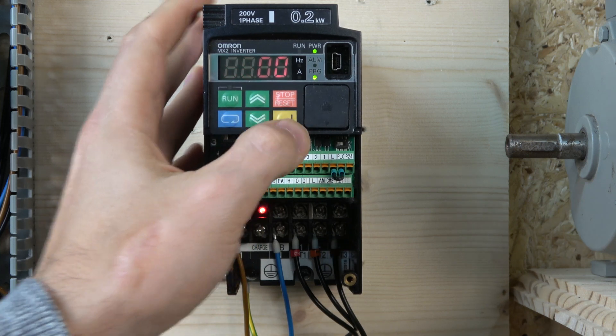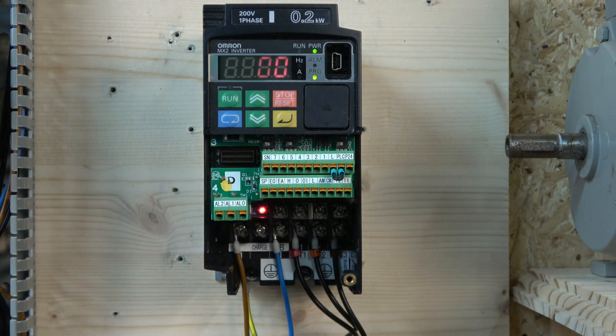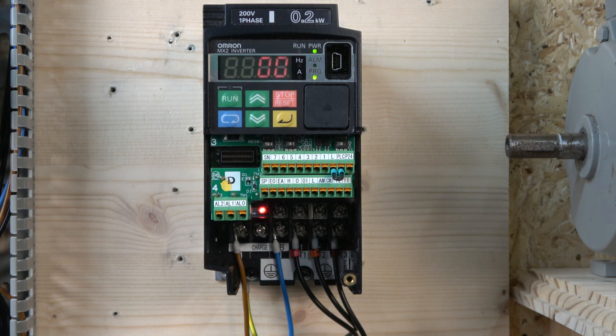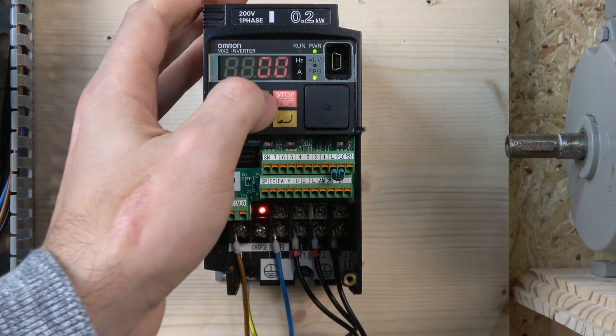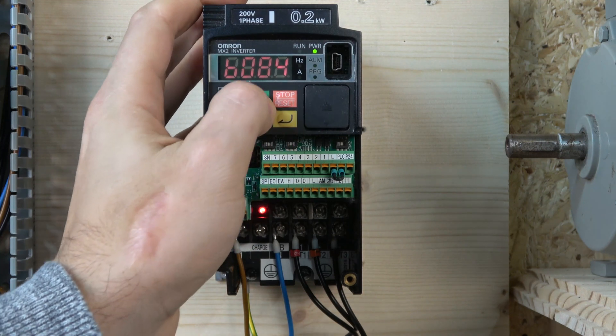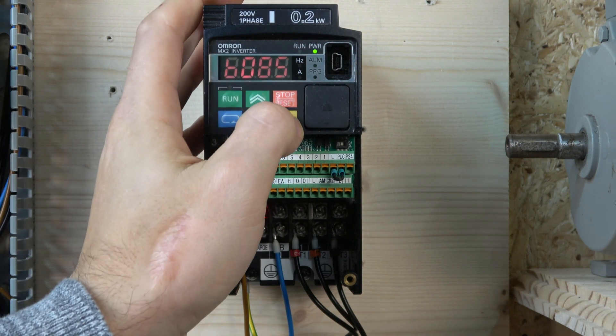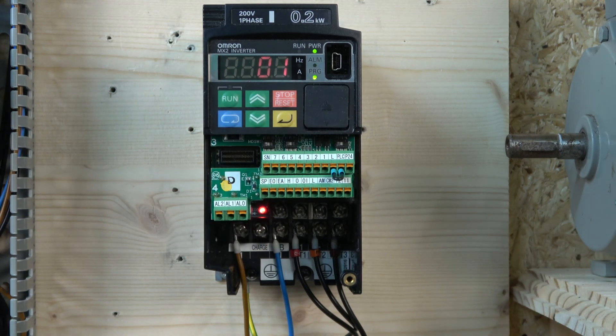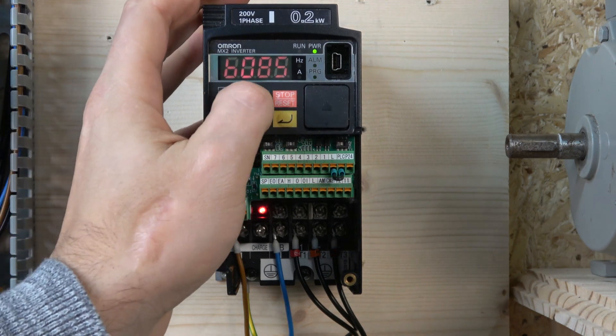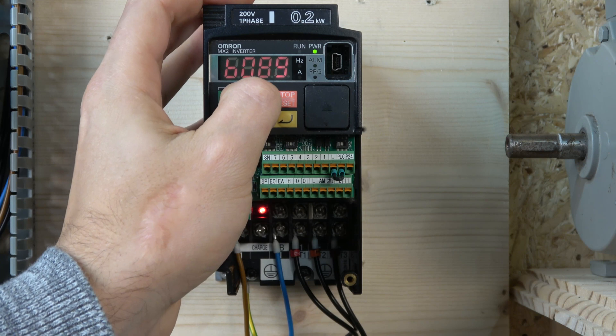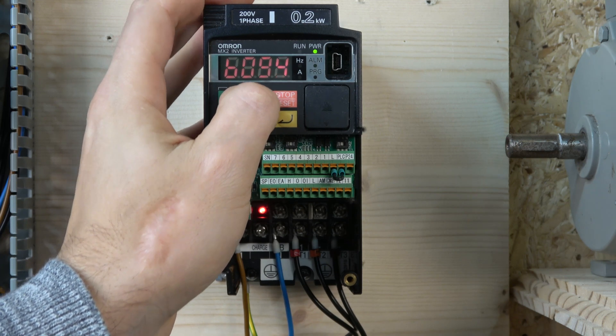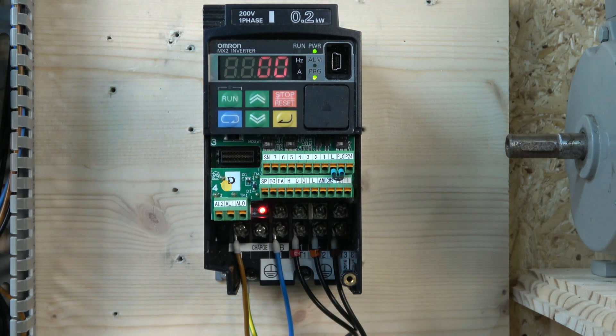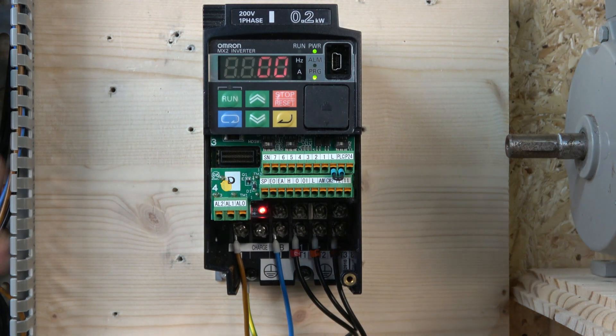In B84, this is where you choose what sort of initialization you want to do. We're going to do complete - we're going to wipe the trip parameters, the trip monitor parameters, and the drive program. We're going to wipe the whole thing off, so change that to 4 and enter. The next one you need to check is B85. This is where you select between Japan or Europe. By default, this is already set to Europe. The next one is B94.